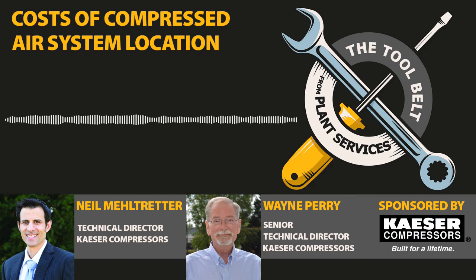What that ends up doing is causing an increased compression ratio on the equipment, which means it's working harder for that same CFM worth of air. We're very involved with the Compressed Air and Gas Institute, CAGI, and those data sheets are really pivotal in helping end users figure out what compressors they need and what the key performance index, specific power, is. If you're running these compressors hotter, if there's not enough air into the room or removal of that air, you could throw the CAGI data sheet out the window, because your power consumption is going to increase 5-10%, and your reliability is going to be lower. And that's when customers start screaming, "Hey, what's wrong?"